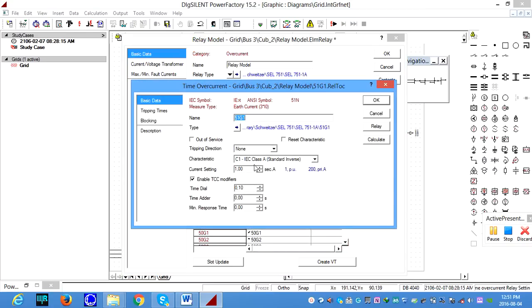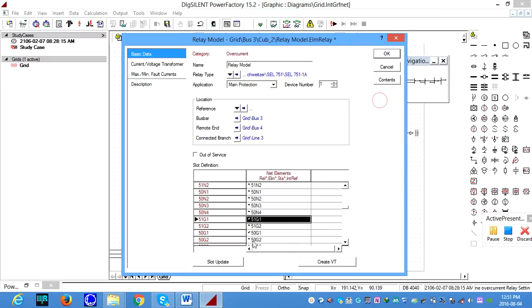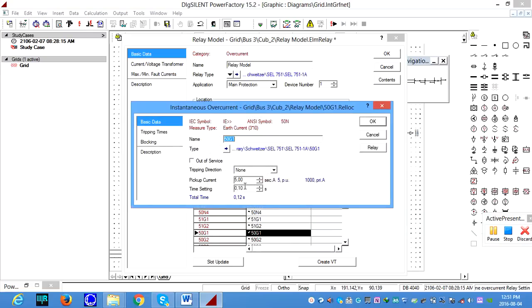And we come to the ground element. For the ground element, IEC standard inverse, current setting is 1 ampere, time dial is 0.10 seconds. And for the definite characteristics of the ground element, pickup is 5 amperes and the time setting is 0.1 seconds. But you can see this is 0.1 seconds, but the total time is 0.12 seconds. This 0.02 seconds will be the operating contact relay time.